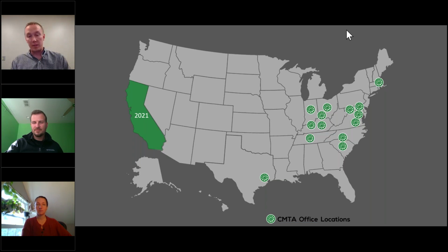Yeah, there are. We will put an emergency shutdown in place, more or less—we do a lot of work in Houston, Texas, as you can see with one of our offices, and there are a lot of chemical plants in that area. So we implement an emergency shutdown button in the building so that if there are pollutants, chemicals, or smoke from wildfire, you can shut down that outdoor air. Not a great long-term solution, because you want that outdoor air, but it's a temporary fix if there's something going on outside your building that you don't want pulled in.